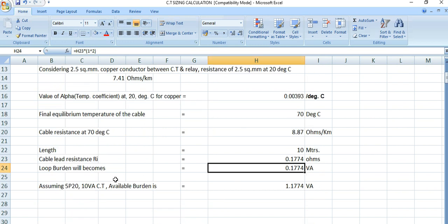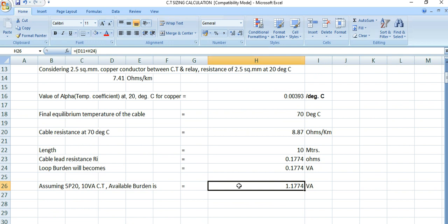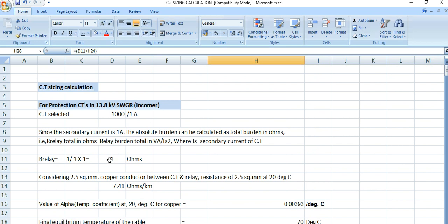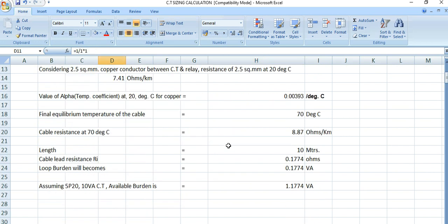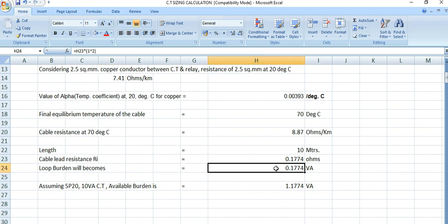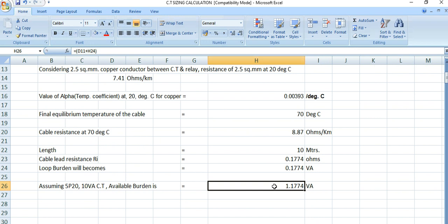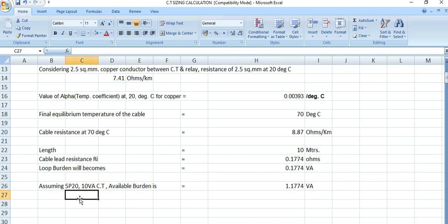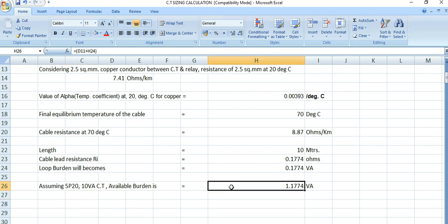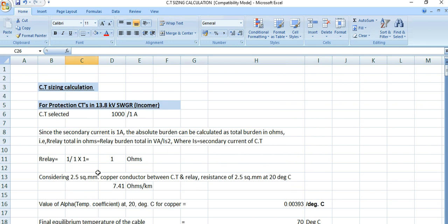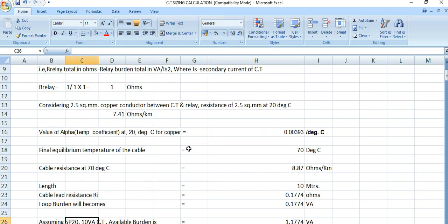The total CT burden equals the relay burden of 1 ohm plus the loop burden of 0.1774, giving a total of 1.1774 VA. If we select a protection CT of class 5P20 with a 10VA burden rating, the actual CT burden is 1.1774 VA — so this 10VA CT is appropriate for this 13.8kV incoming feeder application.